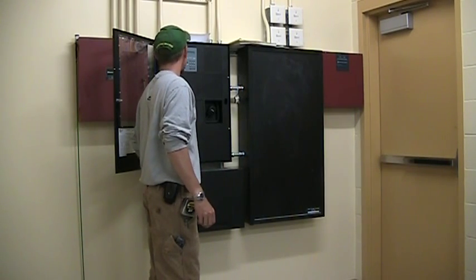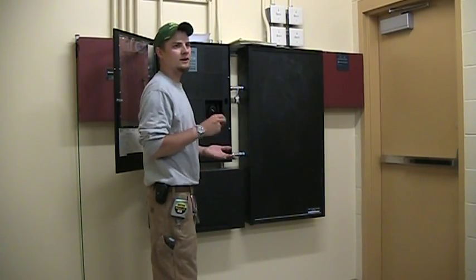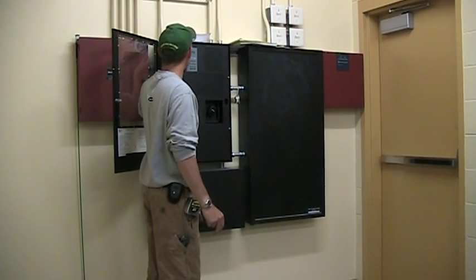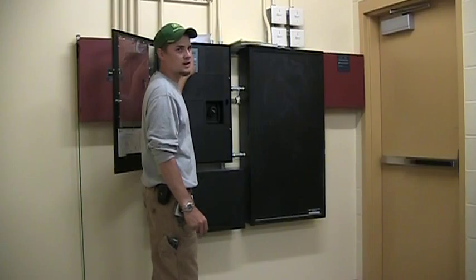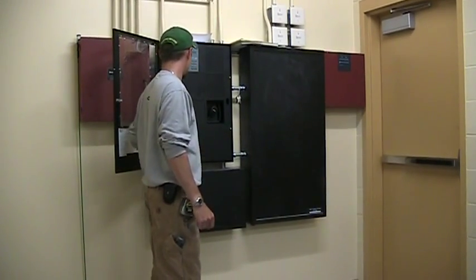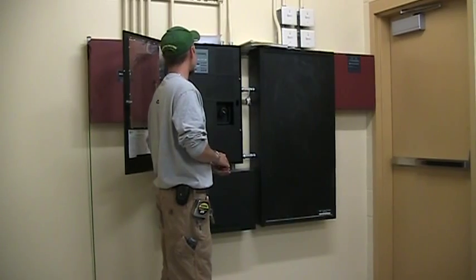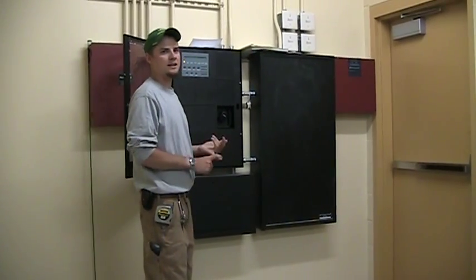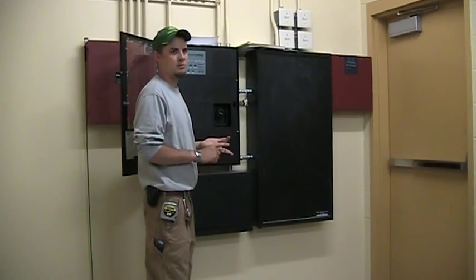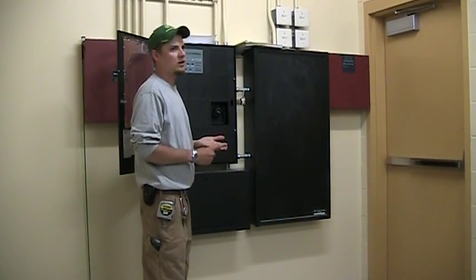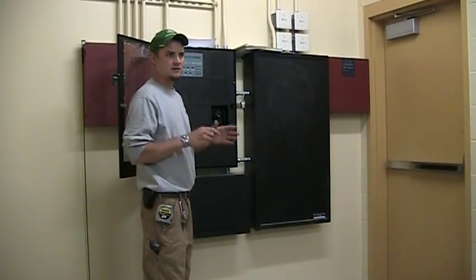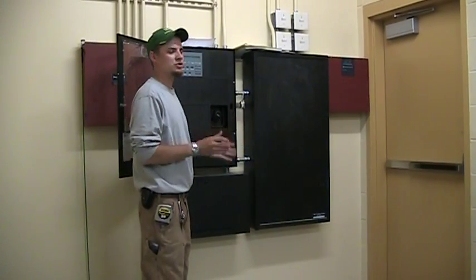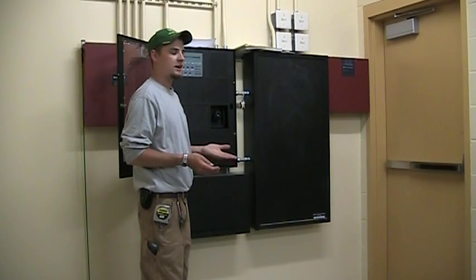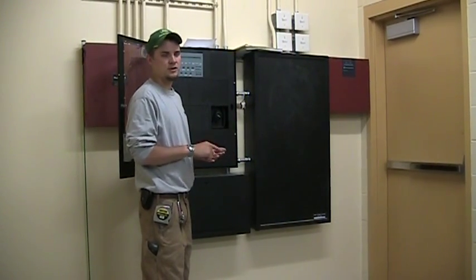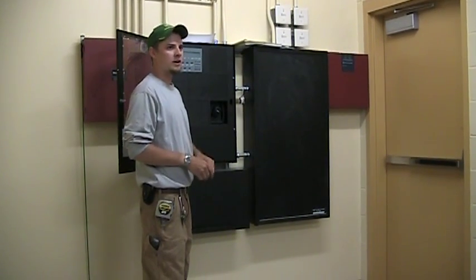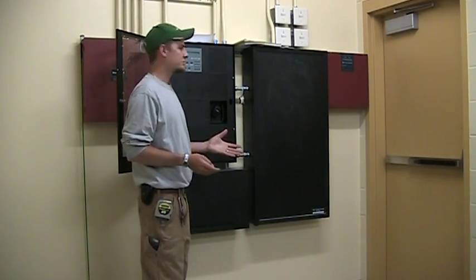This is an addressable system, so if a device goes off, it should give you a description of what it is and where it is. The only things that will set an alarm off are a device like a heat, a smoke detector, a pull station, a water flow, or the kitchen ansul system. There's other devices out there, and they will show a trouble because they're like a supervisory. Anything else to do with your sprinkler system, tamper switches, stuff like that, will come in, but it won't set the alarm off. It'll set it off as a trouble.